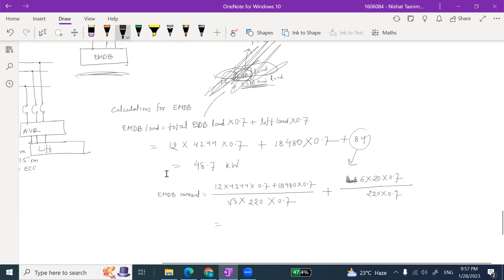Why have we used √3 here? Because you can see that we're taking the connection from 3-phase lines, right? So for the EMDB current, this current, and this cable, you need to use √3. But for the 6 lifts we use single phase there, right? Can you calculate and tell me the total value? 182.7.